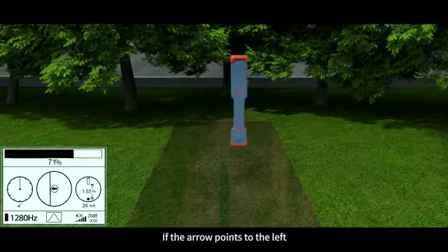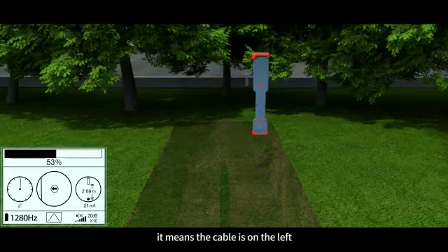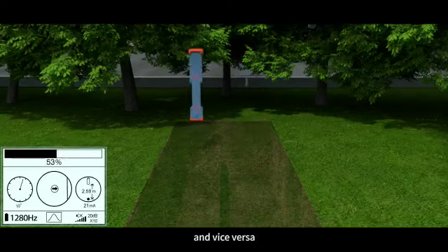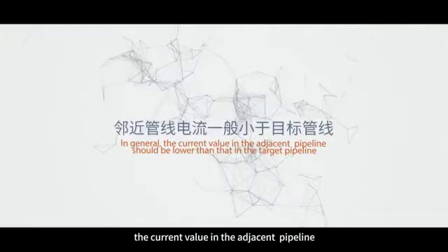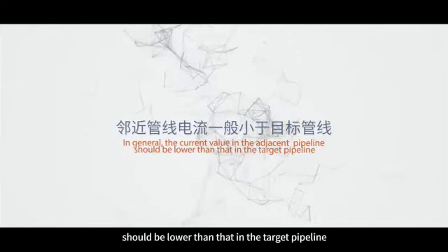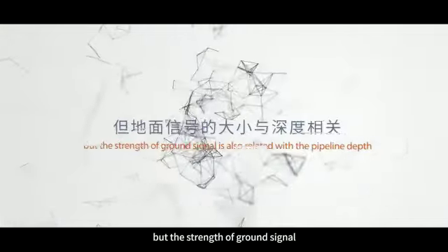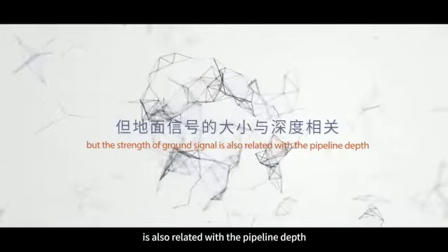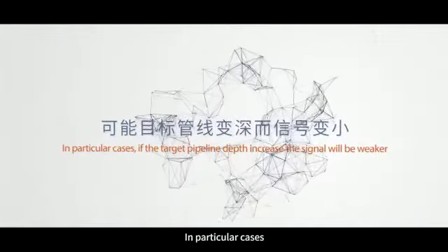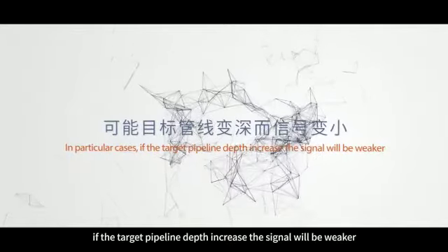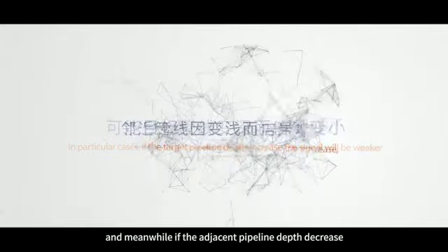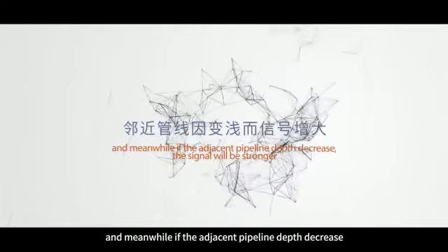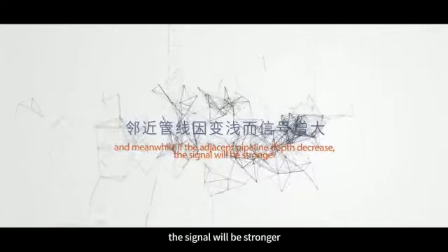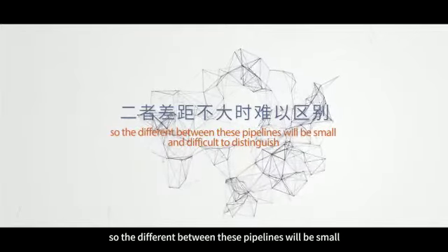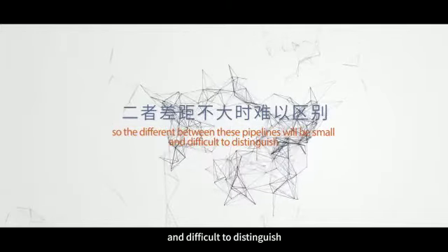If the arrow points to the left, it means the cable is on the left. It should be moved to the left and vice versa. In general, the current value in the adjacent pipeline should be lower than that in the target pipeline. But the strength of the ground signal is also related to the pipeline depth. In particular cases, if the target pipeline depth increases, the signal will be weaker, and meanwhile, if the adjacent pipeline depth decreases, the signal will be stronger. So the difference between these pipelines will be small and difficult to distinguish.